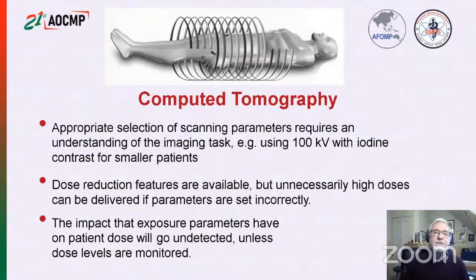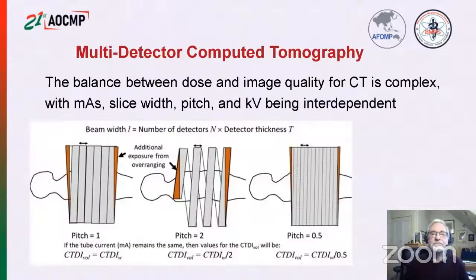Now turning to computed tomography, appropriate selection of scanning parameters requires understanding of the imaging task. So you might use 100 kV with iodine contrast for smaller patients, but that wouldn't be appropriate for larger patients. Dose reduction features are available, but unnecessarily high doses can be delivered if these aren't used correctly. And the impact that the exposure parameters have on patient dose will go undetected unless dose levels are monitored.